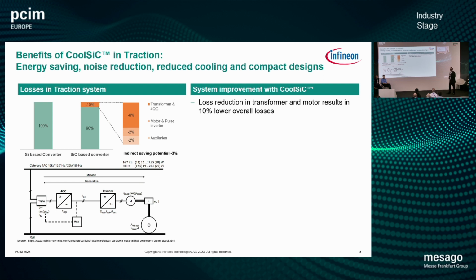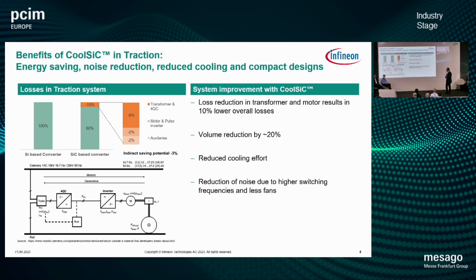What it clearly brings overall is 10% lower losses in the transformer and the motor, a volume reduction of 20% because of the smaller size of the systems, and also a reduced cooling effort, because silicon carbide has very low losses, which means the cooling can be optimized to have smaller housings. And when you are operating at higher frequency, there is a benefit of reducing the losses and thereby also reducing the fan in the system. So you can go from a forced air-cooled system to a naturally air-cooled system just by having the lower losses of silicon carbide.